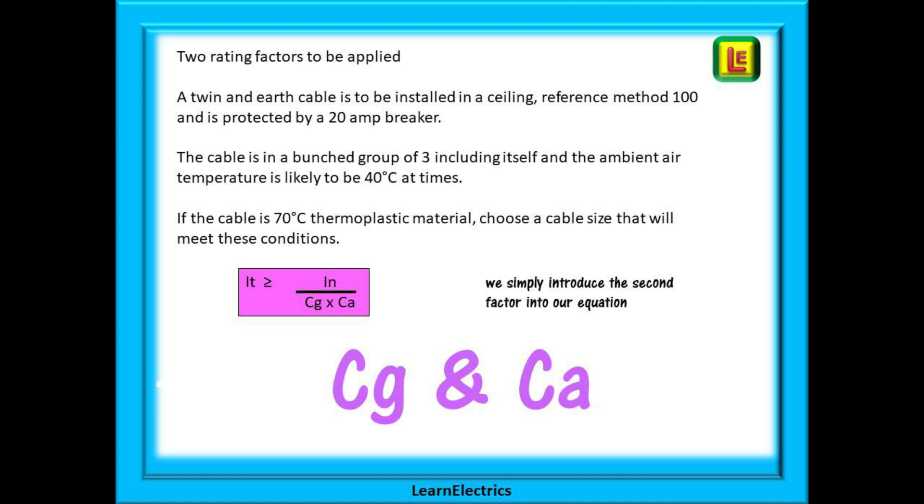A twin and earth cable is to be installed in a ceiling using reference method 100 and it is protected by a 20 amp breaker. The cable is in a bunched group of 3 including itself and the ambient air temperature is likely to be 40 degrees centigrade at times. If the cable is 70 degree thermoplastic material choose a cable size that will meet these conditions. It is the same formula as before except that the breaker size IN is now divided by CG and CA but it is still easy.